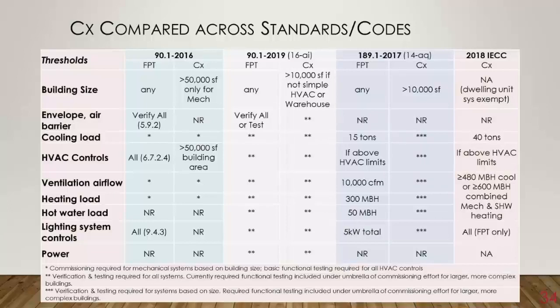2018 IECC, which is the code adopted by many states, and ASHRAE does try and make an effort to go over to the hearings in IECC and get things adopted that come up in 90.1. So there's pretty good correlation between the two sets of energy efficiency codes. 2018 IECC also has these requirements that are based on cooling capacity, heating capacity. Here they combine the mechanical and service water heating. And if you're over one of those, either cooling or heating limits, then you're required to do it. So you could have a building with no cooling whatsoever, but if your heating load is big enough, then you would have to do it.